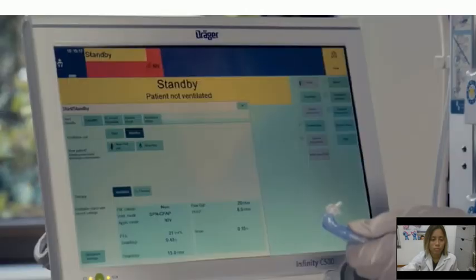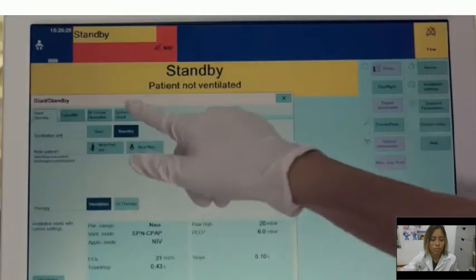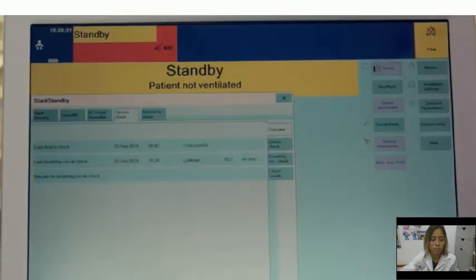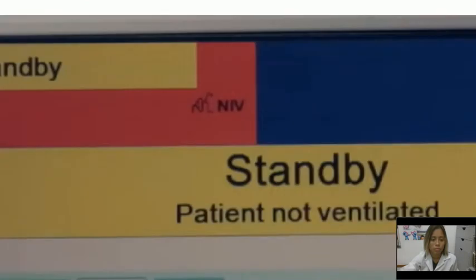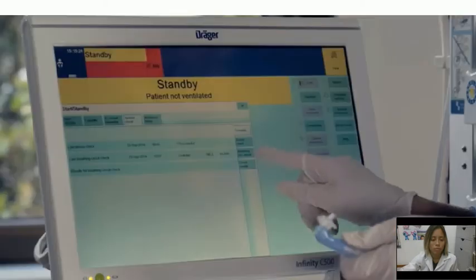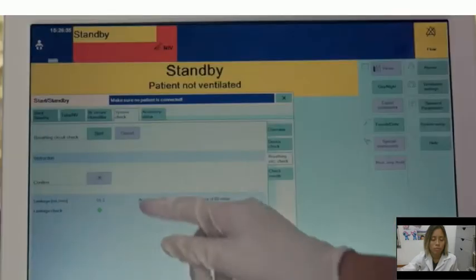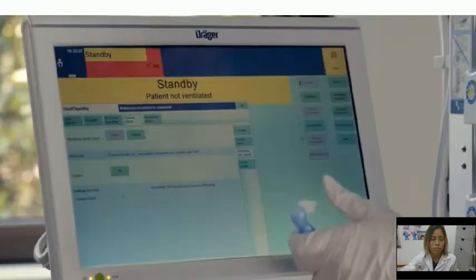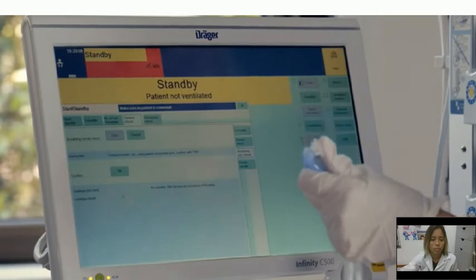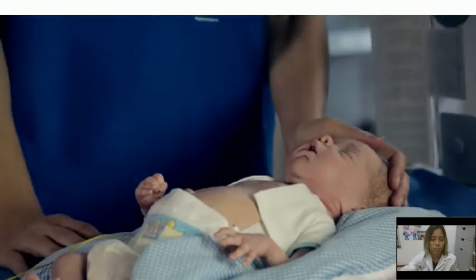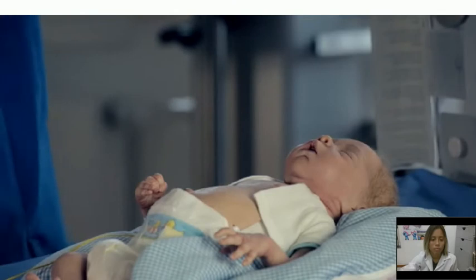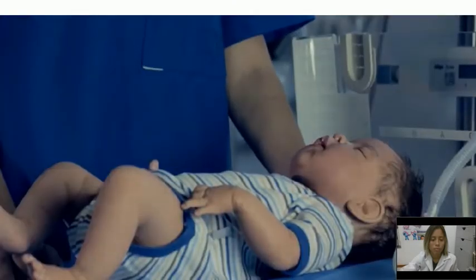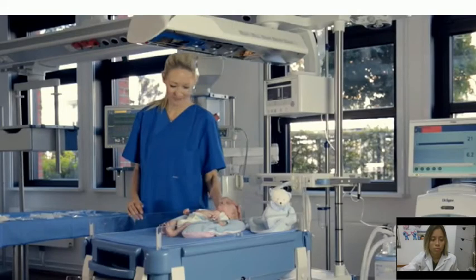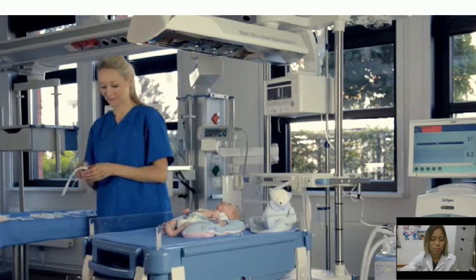To begin, prepare the ventilator for use. 1. First perform a system check. 2. If the system passes the check, then set the device for use in NIV, non-invasive ventilation mode. 3. Once the mode is set, then perform the ventilator circuit check. In this video, we will show 2 different size patients, a neonate and a full-term infant, to demonstrate the application of the prongs and the mask, respectively, with the BabyFlow Plus.